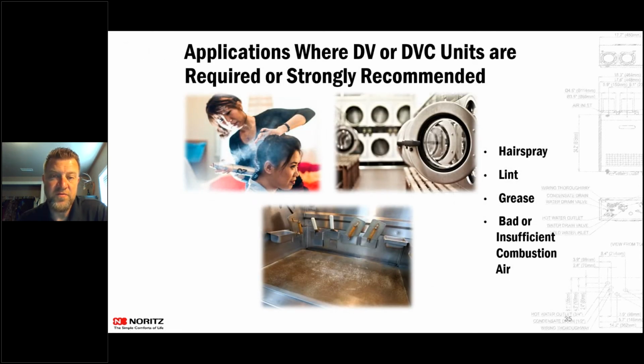Areas where a direct vent or direct vent concentric is very highly recommended are salons, laundries, restaurants, places where hairspray, lint, grease, or there's just not enough combustion air within those spaces for that unit to run properly. Can't tell you how many times we've gone to places like restaurants or hair salons, and those fans have pulled in the hairspray and the lint and the grease and all that stuff, and it's just gummed up that whole fan to where it's spinning and going, but it's not pushing any air. So in those areas, it's very highly recommended to pull that combustion air from outside.